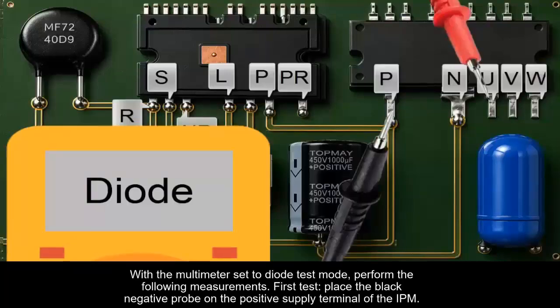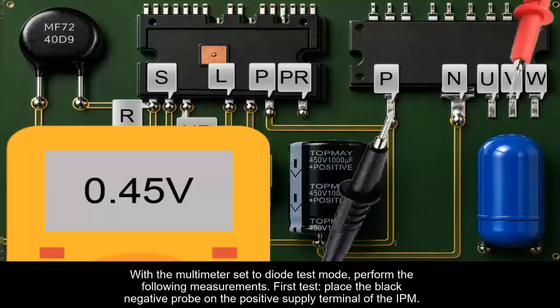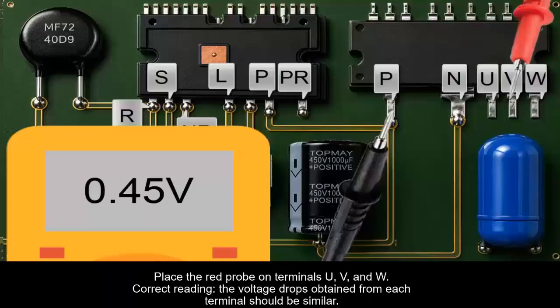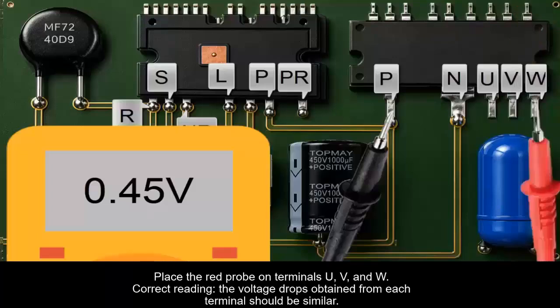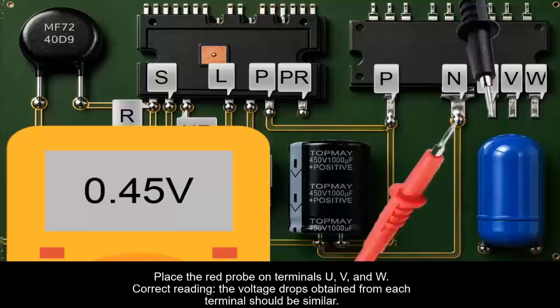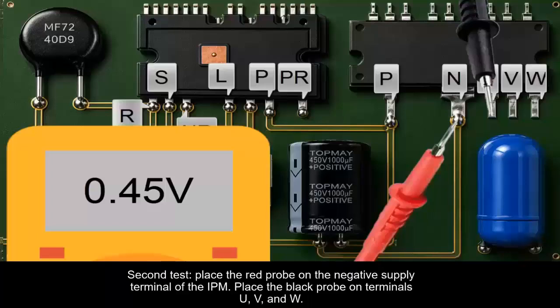First test. Place the black negative multimeter probe on the positive supply terminal of the IPM. Place the red probe on terminals U, V, and W. Correct reading: the measurement voltages obtained from each terminal should be similar or virtually identical. Second test. Place the red probe on the negative supply terminal of the IPM. Place the black probe on terminals U, V, and W. Correct reading: as in the previous test, all measurement voltage drops should be similar.